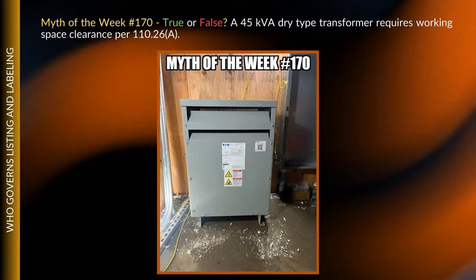Now the other question to ask is, what's a transformer? Don't say you need working space in front of a transformer — once again, you got somebody with no real life field experience who doesn't understand 70E. When you get in and start looking at clearances around transformers, the reason it was discussed in the first place is when they were going to go in and do an infrared scan on the transformer. That's where all this comes from — it had nothing to do with anybody ever getting in the transformer to measure the voltage. Of course you'd do it at the panel board. But once again, he doesn't know the 70E document and gets in to talk about things he doesn't know anything about. Go ahead and go on, because I'm going to show some of this stuff.